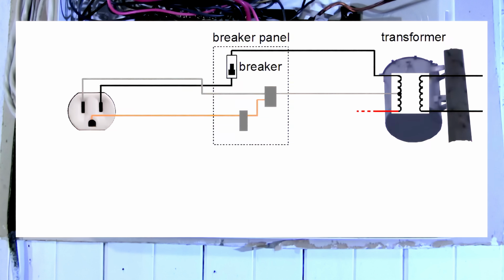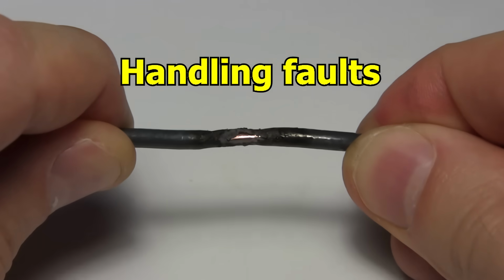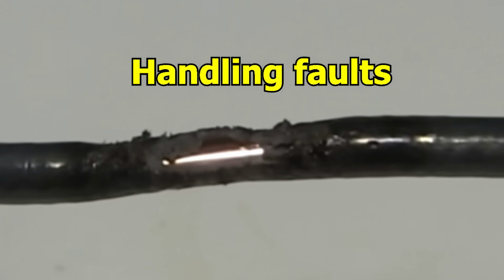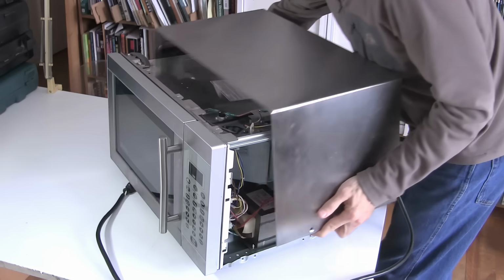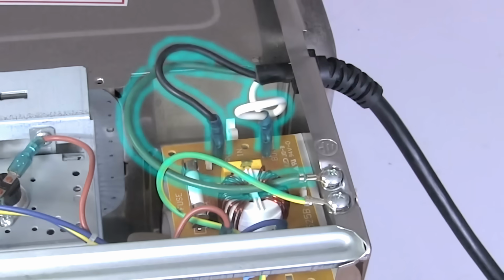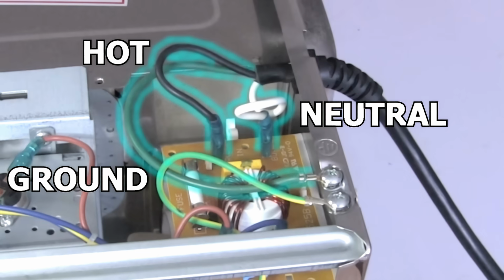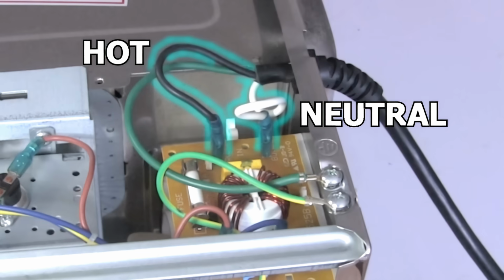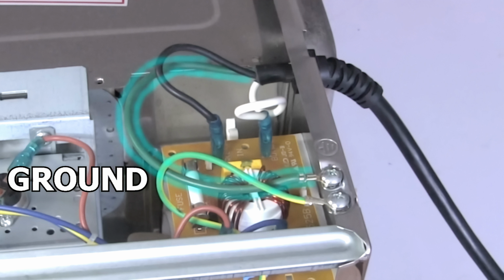Our diagram now looks like this, with the ground wire going to a ground bar and then onto the neutral bar. But why is the ground wire connected to the neutral bar like that? That's in case you have a break in the insulation covering a wire somewhere. That break can cause a fault, such as in this microwave oven. 3 wires enter the microwave oven. Those 3 wires are connected to the 3 prongs of the plug, hot, neutral, and ground. As we said, the electricity flows through the hot and neutral wires. The 3rd wire is the ground wire. The ground wire is connected to the metal case, and normally no electricity flows through it.